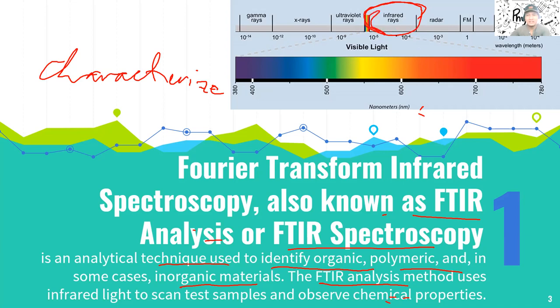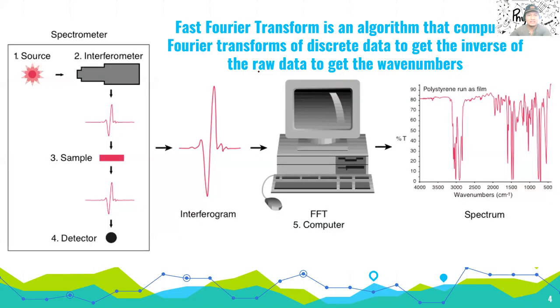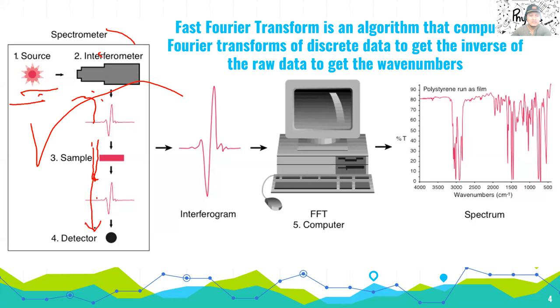What's nice about infrared is it's not harmful. So first, inside the spectrometer, you have a light source, and then there's an interferometer that regulates the frequencies presented to the sample. After that, there is a detector which detects how much light is being absorbed by the sample. The interferogram signals are the input to the computer, which uses a fast Fourier transform to generate the spectrum.